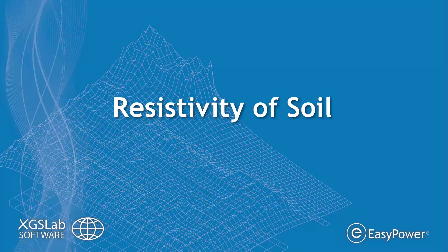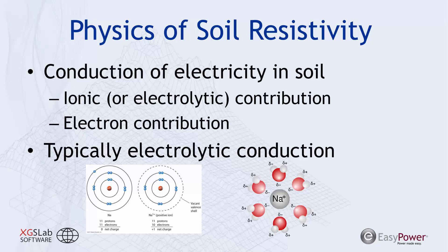First, let's cover the basics of soil resistivity. Primarily, we have two types of electrical conduction in the soil: the electrolytic or ionic contribution, and the electron or electronic contribution. When discussing the electrolytic contribution, we're primarily looking at ions in the soil as the moving charged particles providing current flow. With metals, it's more similar to the electronic contribution, where electrons are the moving particles. For soil or earth, that conduction or resistivity is primarily a factor based on electrolytic conduction.